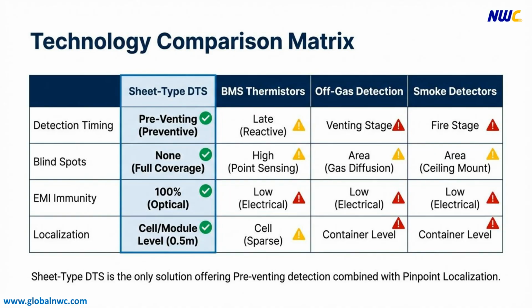Among existing battery safety diagnostic technologies, sheet-type DTS is the only solution capable of detecting early fire signatures during the pre-venting stage before gas venting occurs. By adopting fiber optic sensing, the system completely eliminates electromagnetic interference while providing precise localization with 0.5-meter spatial resolution, enabling full coverage without blind spots. Going beyond the limitations of conventional BMS thermistors and gas or smoke detection methods, this technology delivers the fastest and most accurate pinpoint detection available for battery safety monitoring.